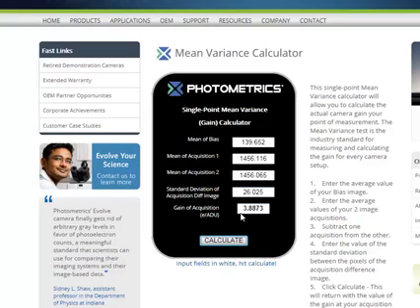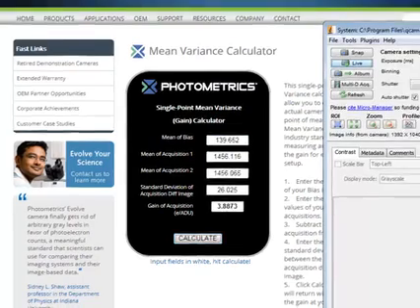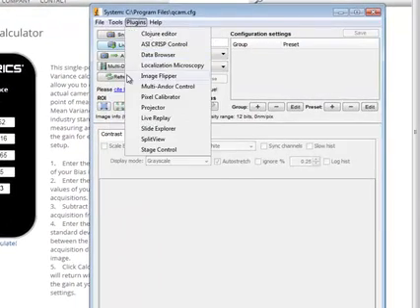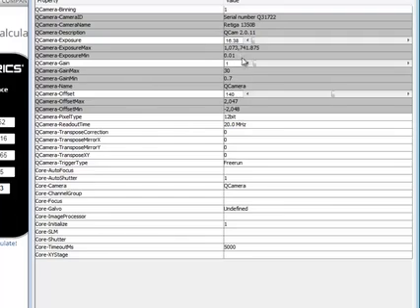A few things we've got to be careful with: the bias image that we take has to have a background to it — it has to have numbers in it, it can't just be zeros. A lot of cameras out there will try and clamp to zero. If you have that, what you want to do is make sure that in a program — say, Micro-Manager — under the properties, you set an offset value. I put in here 140. It doesn't really matter what it is, but you must have an offset.